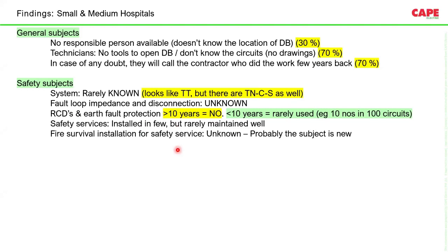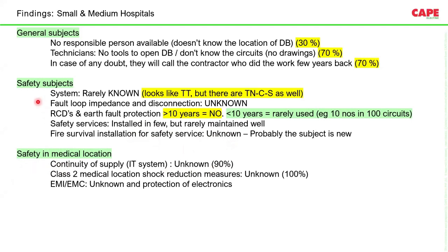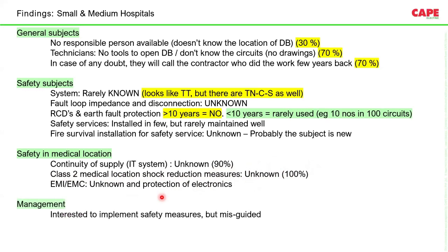Safety services means systems for firefighting or emergency. They are installed, but not maintained well, and most often they are not in working condition. Fire survival installation is very rare. This first part, the safety subjects I have shown, is for the general electrical installation, whereas for the medical location, let's say Group 1 or Group 2, where continuity of supply is necessary, in most cases this subject is unfortunately unknown. For Group 2 medical locations, the shock reduction measures are very, very rarely known. One of the subjects here is supplementary equipotential bonding, which I will explain later. And subjects like EMI and EMC are very much unknown.